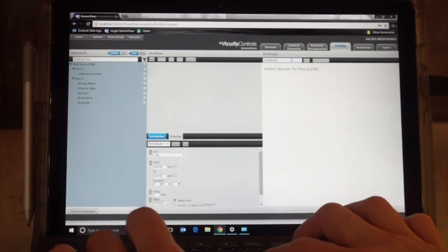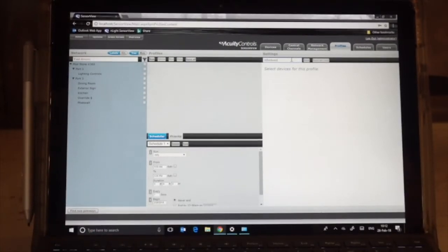After Hours. Something that we haven't really talked about with the nLight system up to this point in the video is that all of the relays are normally closed, electrically held open. What this means is in event of power loss, system failure, hardware failure, all of the relays will default to closed, keeping the lights on. What this means from a scheduling perspective is we don't actually have to tell the lights when to be on, rather we need to tell them when to be off. When don't we want the lights on? So sort of have to think about it slightly the inverse of how you might be typically thinking about your lighting schedule. So we'll call this After Hours.